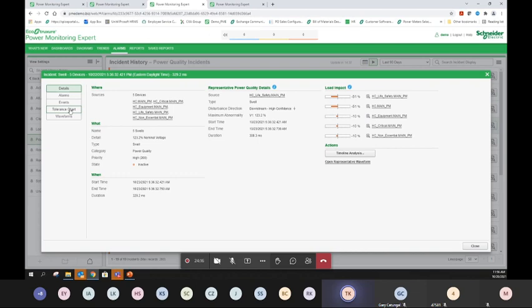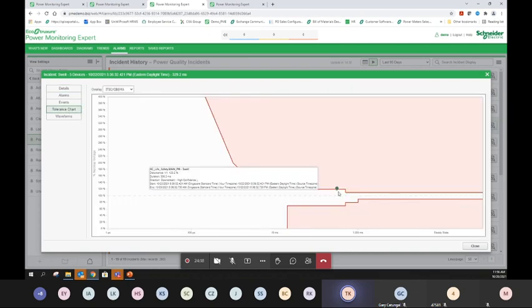Another important thing is the tolerance chart. You can see from here - this is the international ITIC curve, the voltage tolerance, showing whether this is acceptable or not. You can see in the margin it's almost starting to be non-acceptable - it has to be in the white zone. This is automatically calculated, taking the information from the high-end power quality meter, and the software will auto-plot it and tell you, let's say, if it's in the boundary.